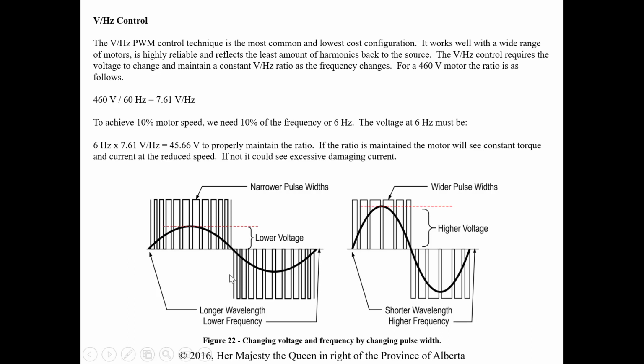Again, think of these diagrams here in the same length of time, same period. So if we have a longer wavelength, we have lower frequency. Narrow pulse width, we're going to get a lower value of voltage coming out of there. If we have wider pulses, we're going to see the IGBT switching on for longer, and we're going to see a higher value of voltage. And we'll have a shorter wavelength at a higher frequency. So this is just talking about the voltage, what's happening to the voltage when we manipulate that frequency.